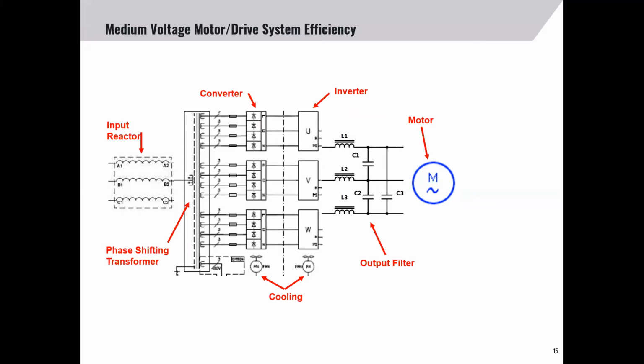However, there are some differences that may affect that value, such as aluminum material versus copper and key components like the input transformer. There are some manufacturers claiming higher efficiencies of their medium voltage drives, even up to 99%. But be careful, as this may not include necessary components shown here in the slide, such as the input transformer or reactor, the converter section, the inverter section, or any output filters that may be required, especially for 3-level output topologies in medium voltage drives. But efficiency is more than just the product itself.